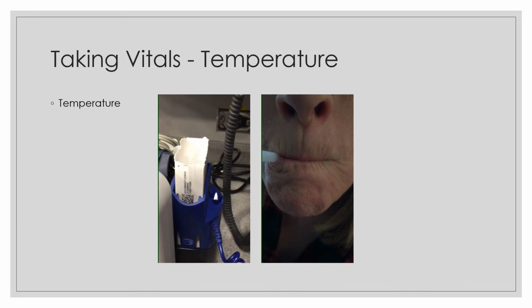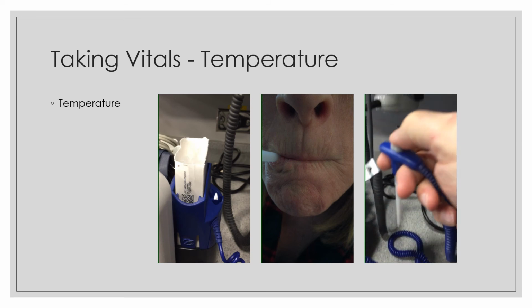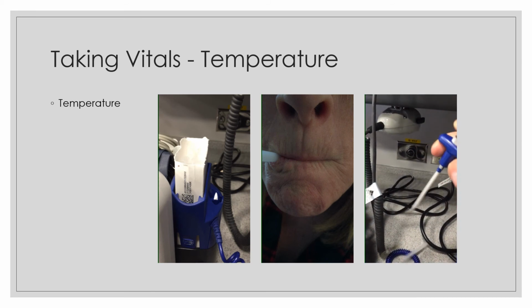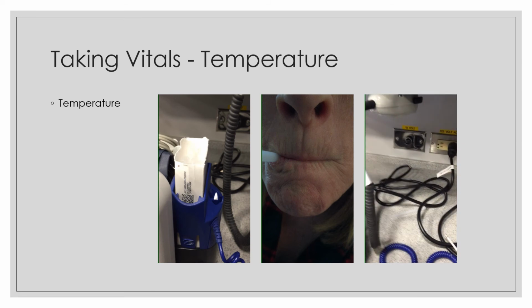The temperature probe has a push button. To discard a used probe, position the probe over a trash receptacle and push the button. The probe cover will eject from the probe. Always remember to discard the probe cover prior to returning the temperature probe into the holder. Failing to do this can cause damage to the temperature probe.